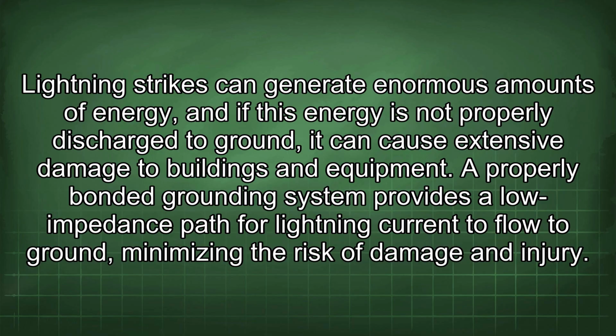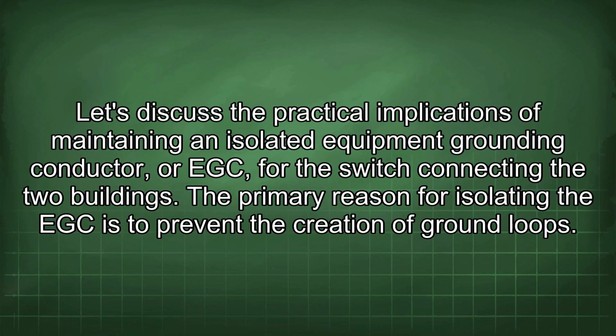Lightning strikes can generate enormous amounts of energy, and if this energy is not properly discharged to ground, it can cause extensive damage to buildings and equipment. A properly bonded grounding system provides a low impedance path for lightning current to flow to ground, minimizing the risk of damage and injury. Let's discuss the practical implications of maintaining an isolated equipment grounding conductor, or EGC, for the switch connecting the two buildings.